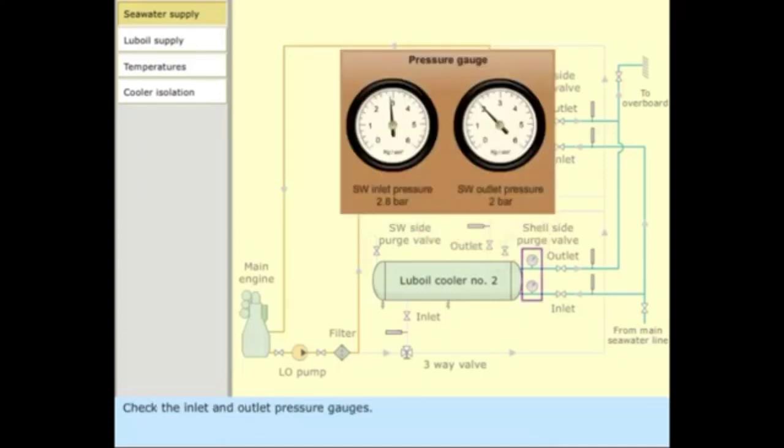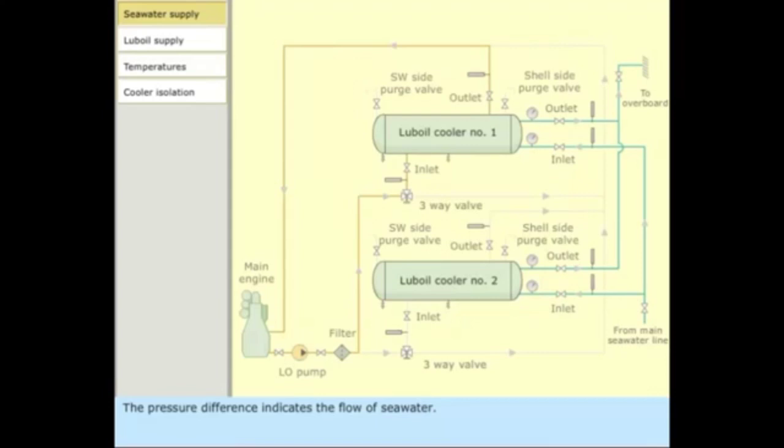Check the inlet and outlet pressure gauges. The pressure difference indicates the flow of sea water. Circulate the sea water for 15 to 20 minutes before allowing the lube oil into the cooler. This is to prevent thermal straining of the cooler components.